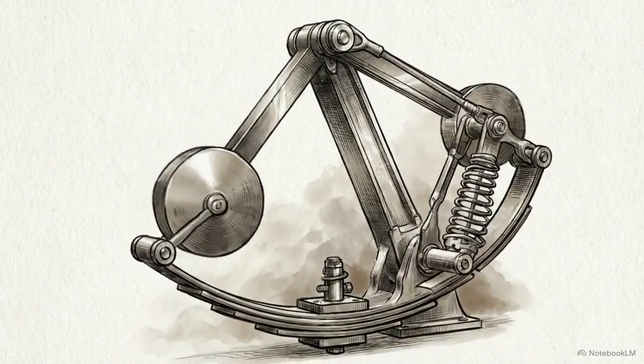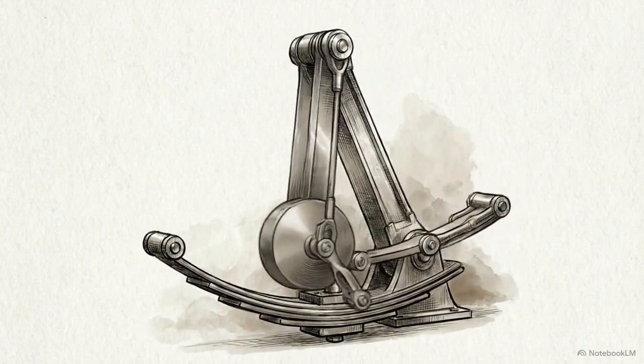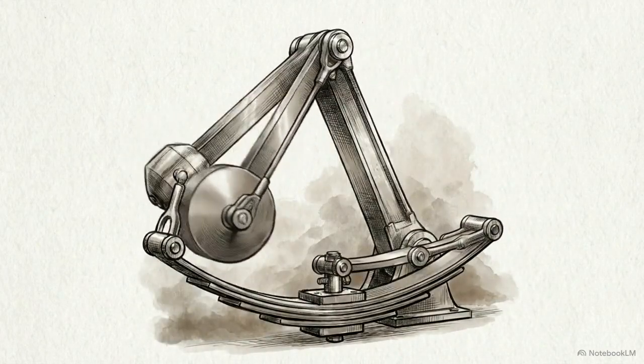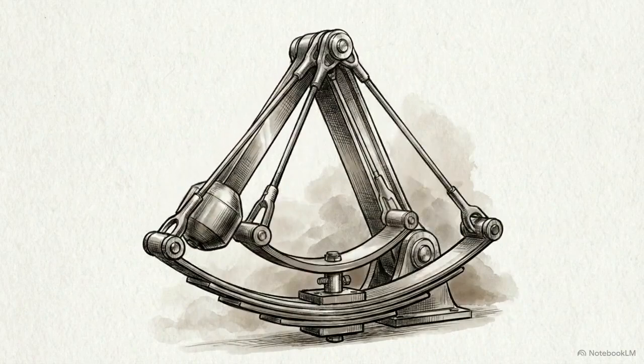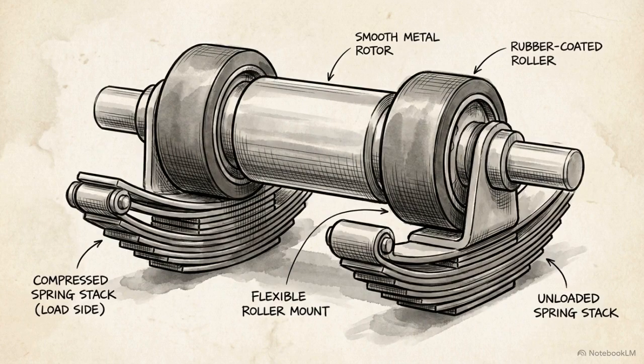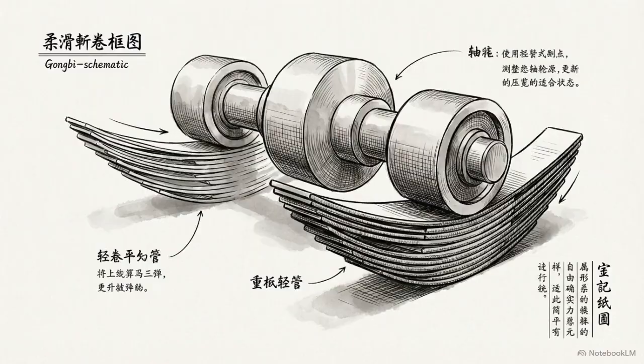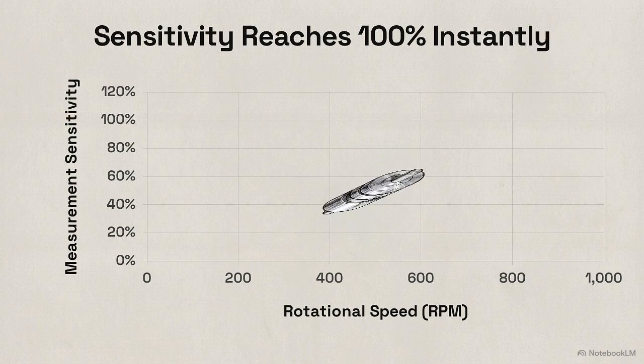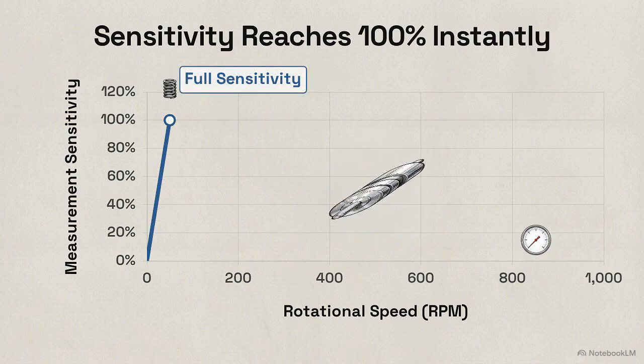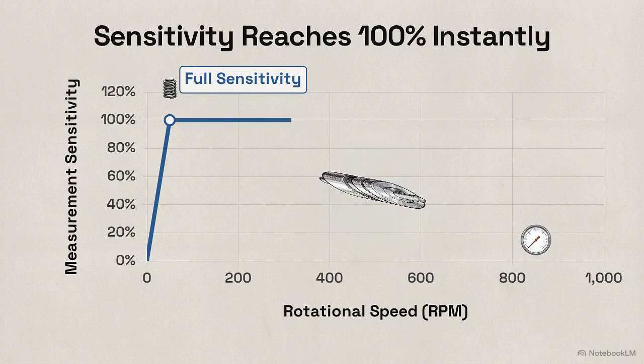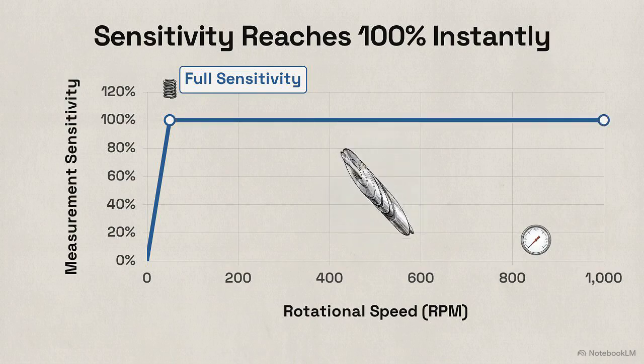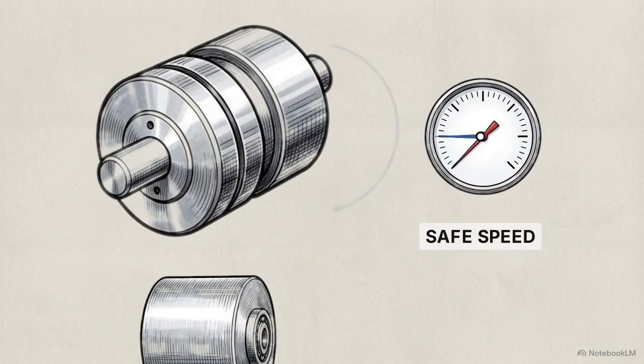The soft-bearing machine takes the opposite approach. Instead of fighting the physics, it embraces them through a suspended pendulum design and flexible roller supports. This structure is self-aligning. Rather than trying to pin the spinning mass in place, the machine's supports move in tandem with the vibration. On this graph tracking measurement sensitivity across rotational speed, you can see how moving with the vibration dictates the machine's range. The sensitivity jumps to 100% as soon as the rotor starts turning and stays elevated across the entire speed spectrum. This allows technicians to run the tests at slower, safer speeds.